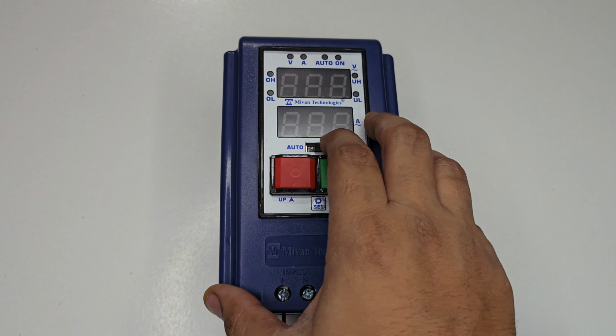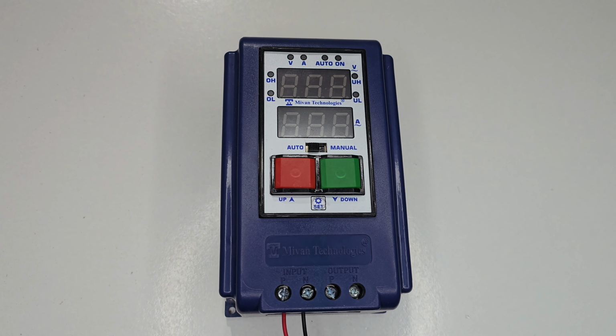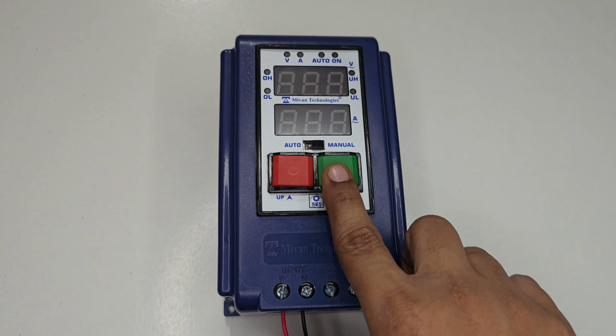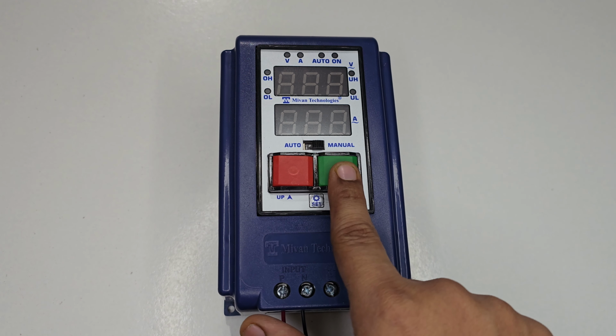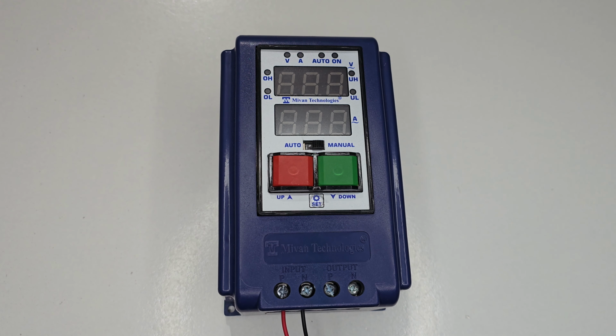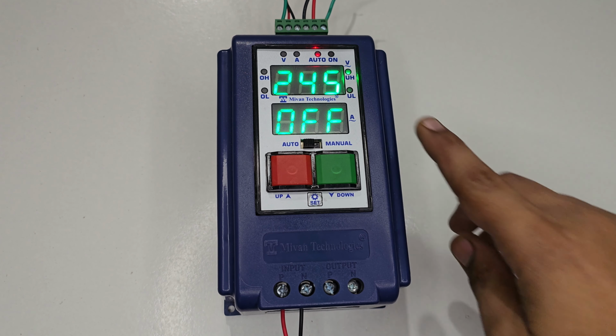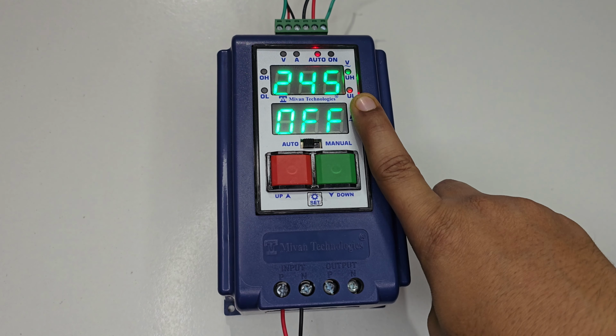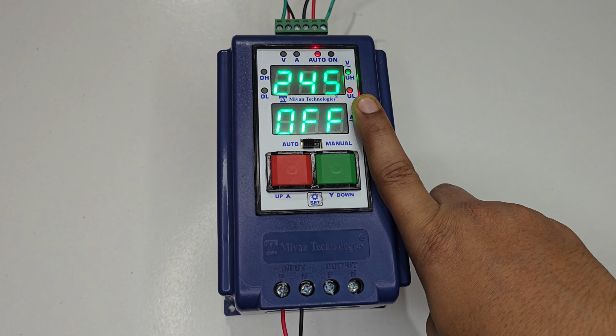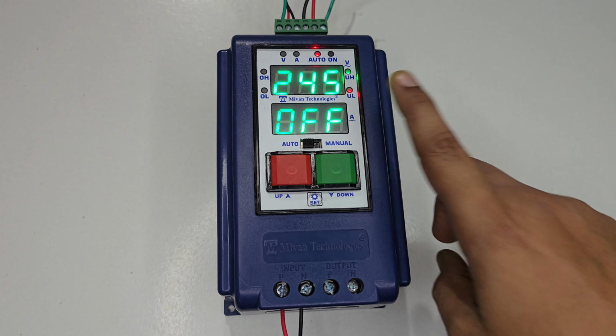Auto and manual mode switch is available. In auto mode, the motor starts and stops automatically based on the water level in the tank. In manual mode, the user can start and stop the motor by pressing the start and stop button of the controller. No additional wiring is required to operate the motor manually. Sensor fault detection is provided. If a sensor fails, the LED starts blinking.